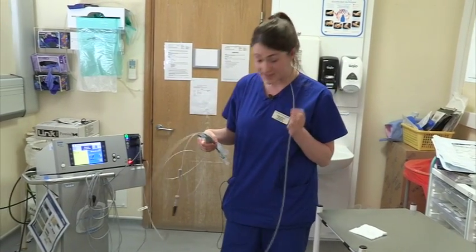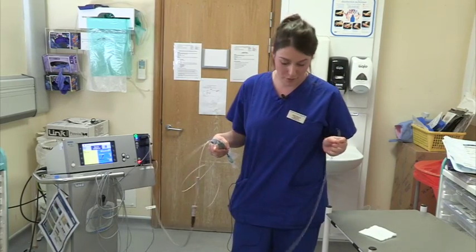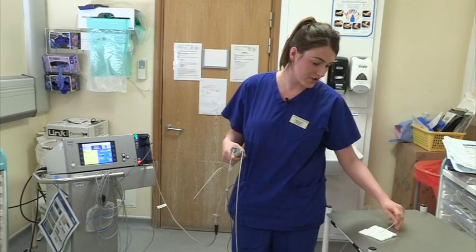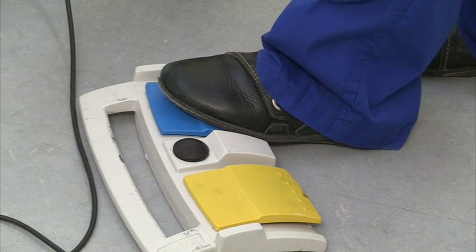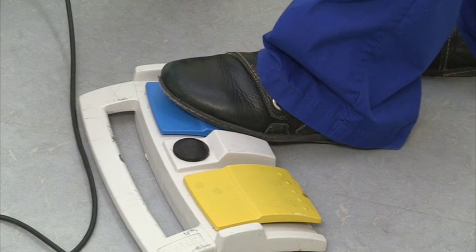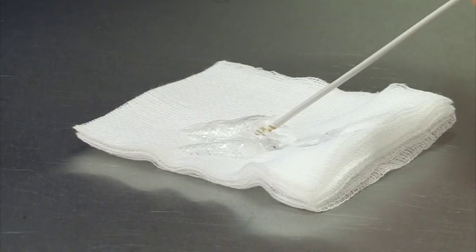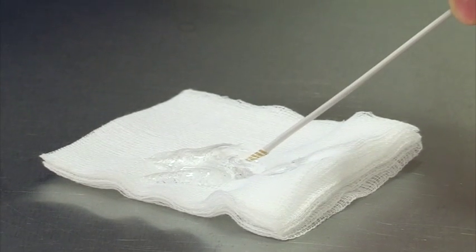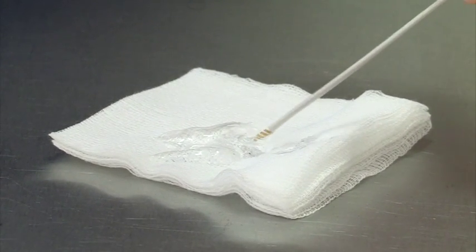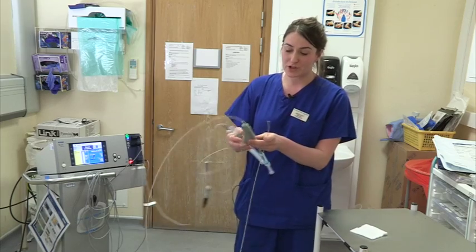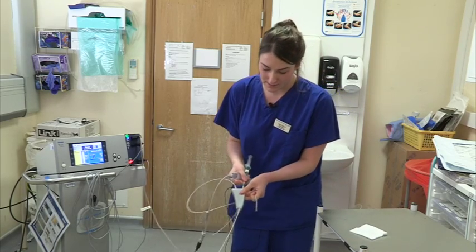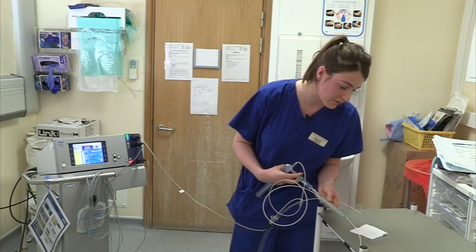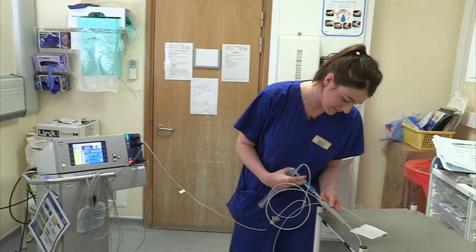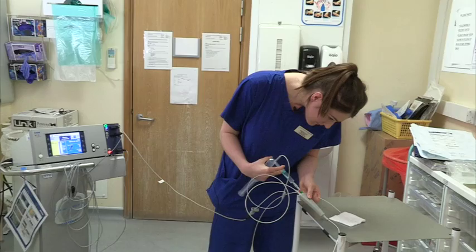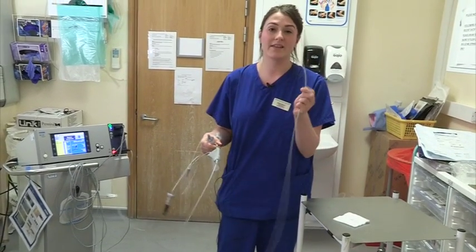So then you just need to test the gold probe. What you need to do is step on the blue pedal and insert the gold probe into the jelly. The endoscopist will know that they need to keep their foot on the blue pedal for at least 8 seconds. And what you should see is some smoke, and you can hear it sizzling, so that is working. So the gold probe's fine to hand to the doctor. If you just want to check your injection, you insert to push and just flush through the channel until you see something come out at the end, which it is, and then you can hand this to the doctor.